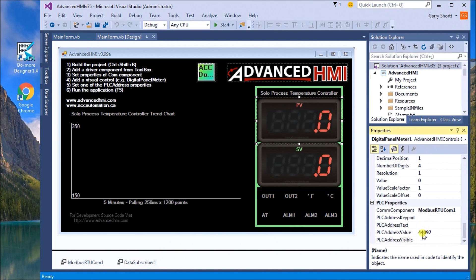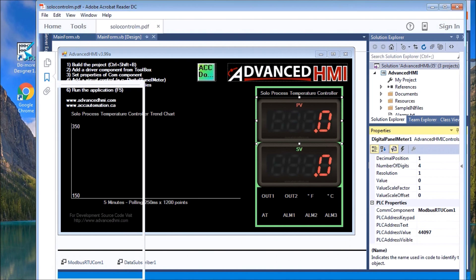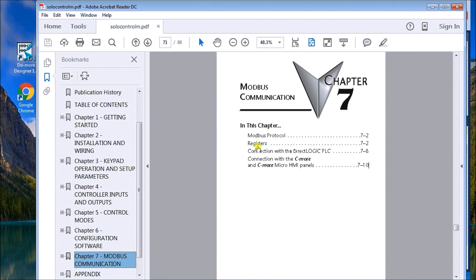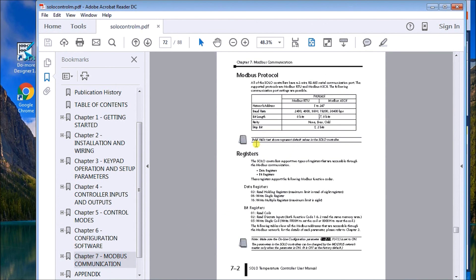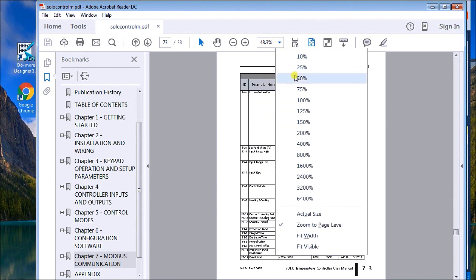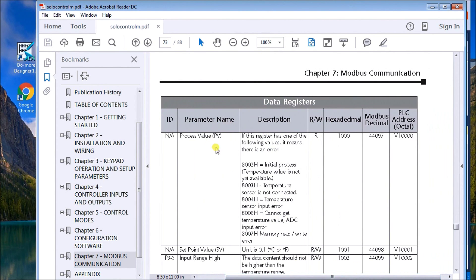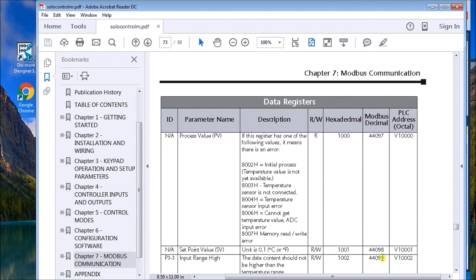The PLC address is 44097, and in order to get that, if I call up the manual and go to chapter 7 Modbus communications, you'll see the registers right here. I'll blow this up a little bit so my PV value (present value) is actually Modbus decimal 44097.